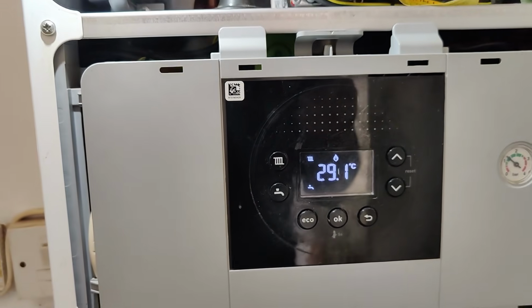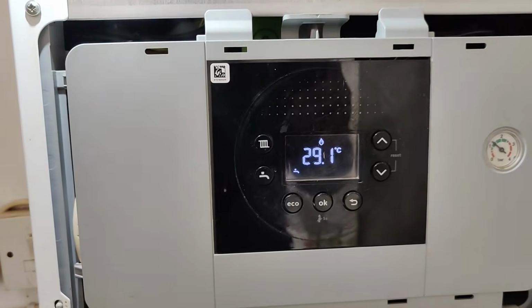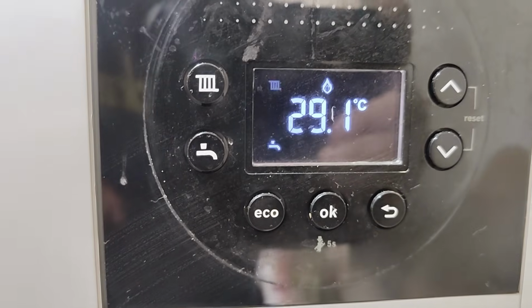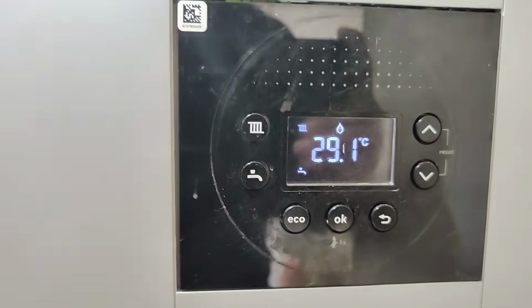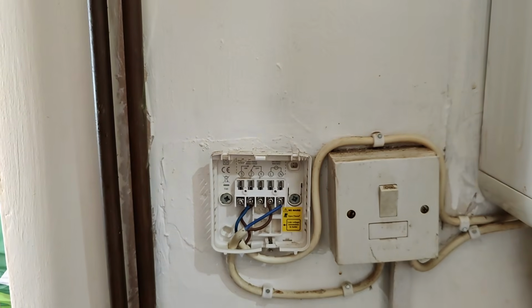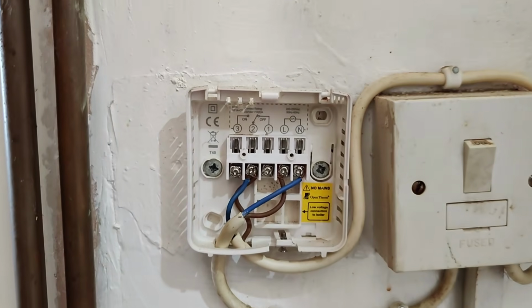I've repaired the cable, and as you can see, we have heating demand. Because we turned the boiler off for a slightly longer period, it's gone to siphon fill mode, so that's going to last a bit. As you can see, the radiator symbol flashing confirms that the demand is back on the boiler. All I need to do is sort the cables on the receiver, because currently it's bypassed, so it's got a constant demand. So I'm just going to put this receiver back on, and that's it.